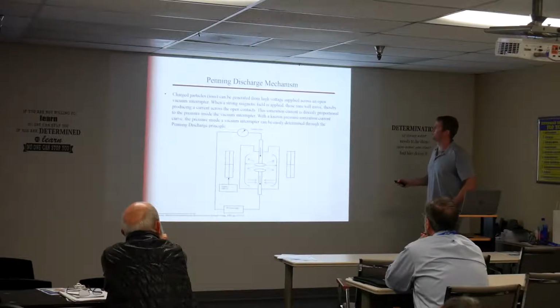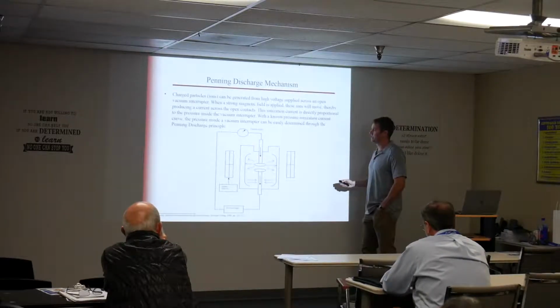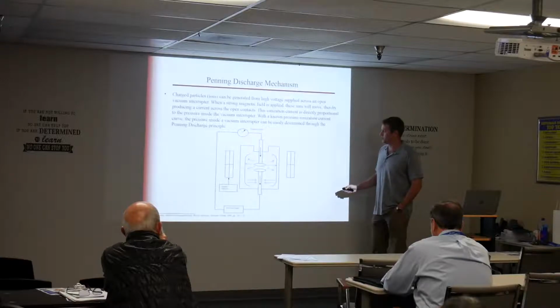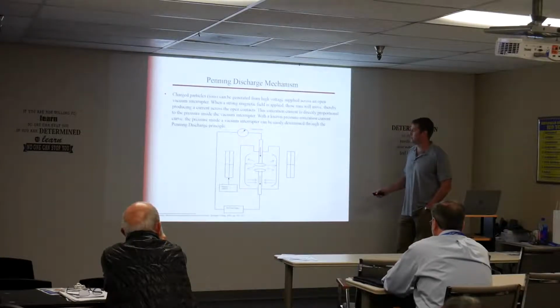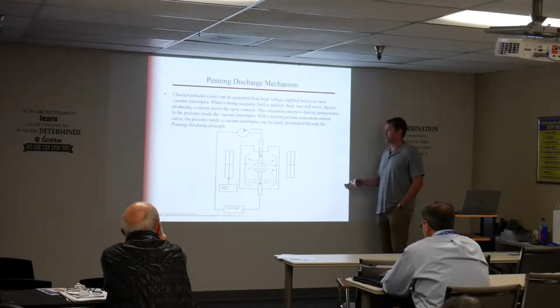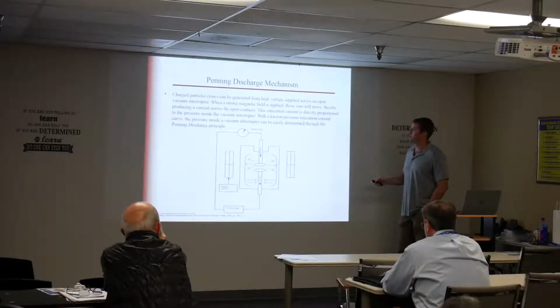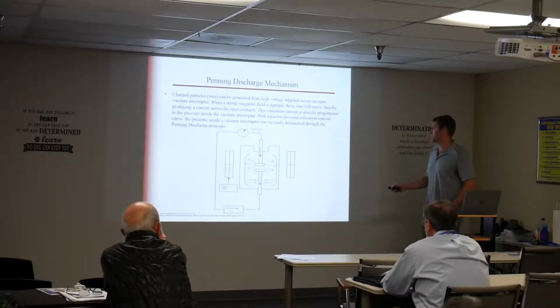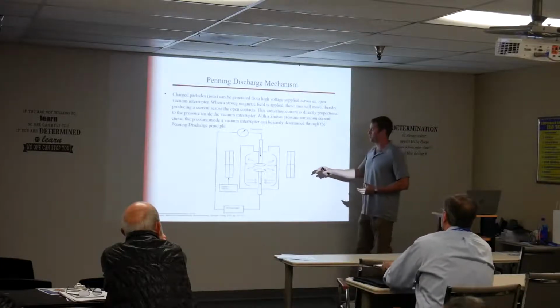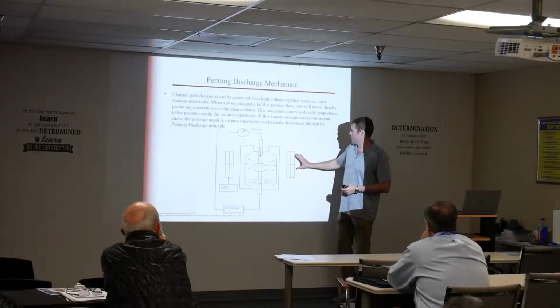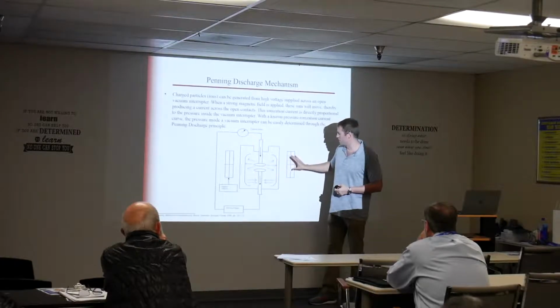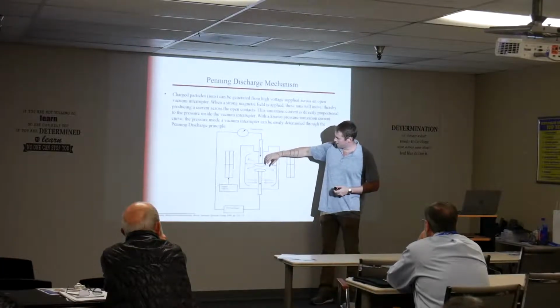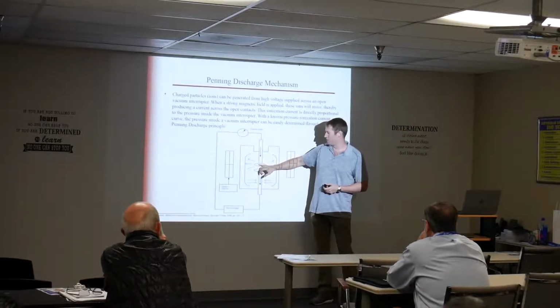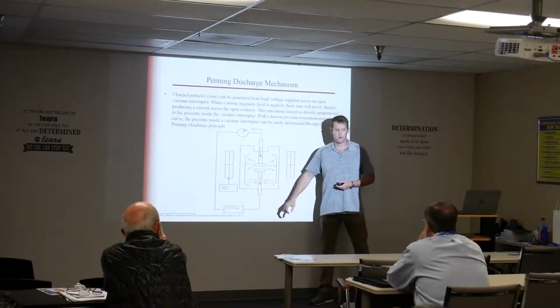So Penning discharge principle is the science behind our test set. So here's an interrupter, two contacts sealed in a canister. So you open the breaker, it opens the contacts. We're applying a high voltage across a set of opening contacts like a high pot. What happens when you do that is whatever gas molecules leaked inside there, you ionize them. So you have charged particles kind of moving around. But what we're doing that makes it a magnetron is we're applying a magnetic field across a set of opening contacts. And using the right-hand rule of magnetism, we force these charged particles across that contact gap and measure it.